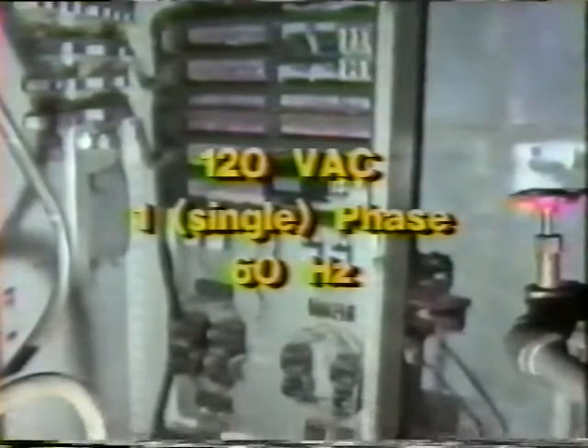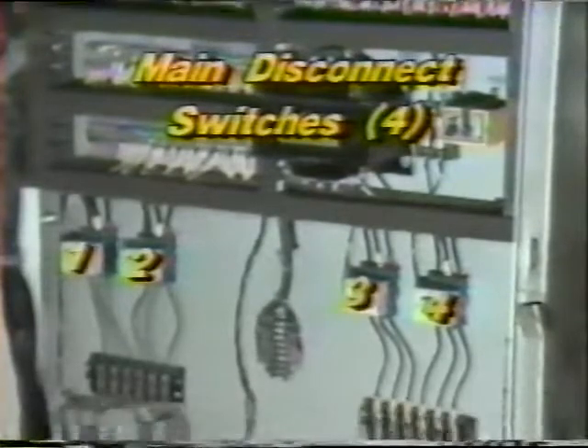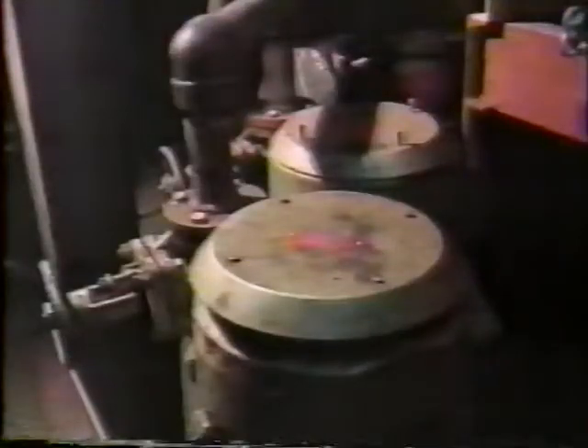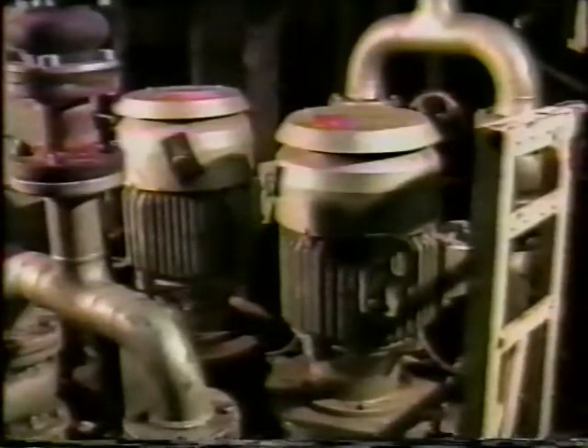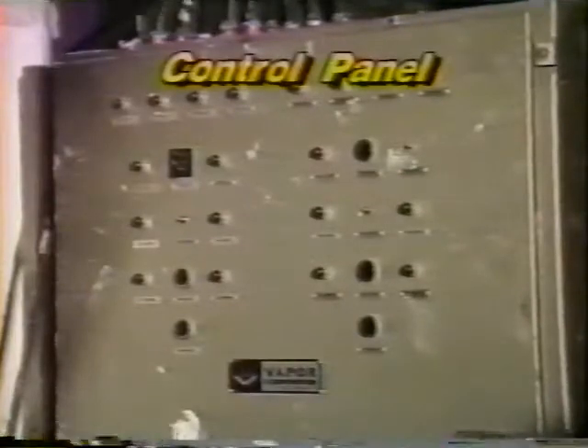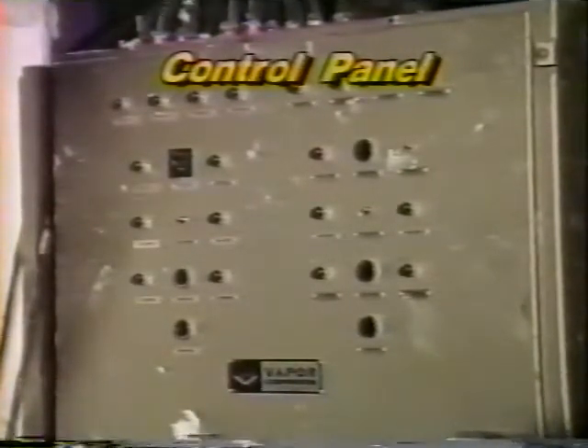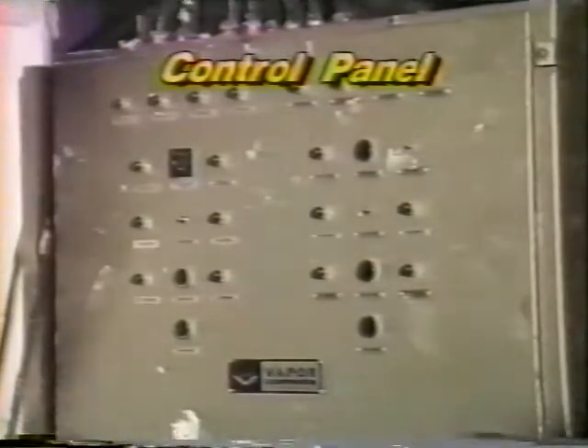The control system requires a 120-volt AC 60 Hz power supply. To operate this system, first all 4 main disconnect switches must be closed. These switches supply main power to the 2 feed water pumps and the 2 recirculating pump motors. A control power selector switch is placed between the control transformer primary winding and the main disconnect switches of the 2 feed water circuits. This allows either of the 2 sources of main power to supply the required 120 volts to operate the integrated control panel. Lights indicate which of the 2 sources are being used. Lights also indicate when each of the 4 main disconnect switches are closed.